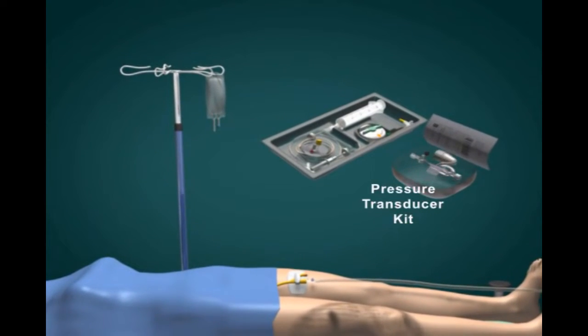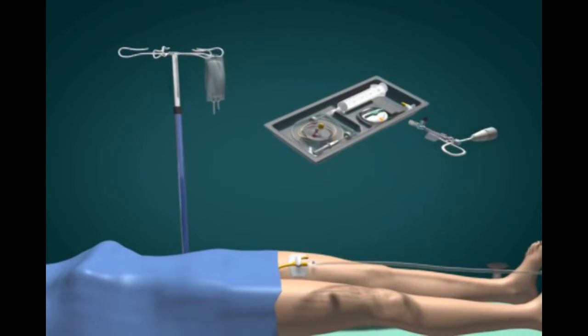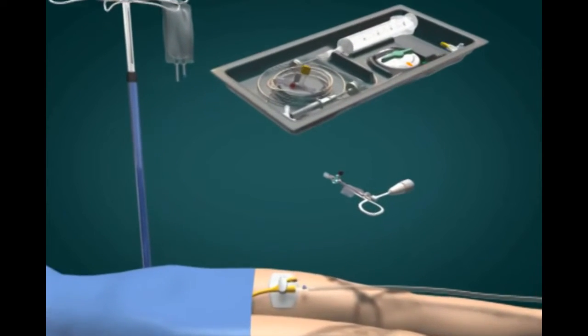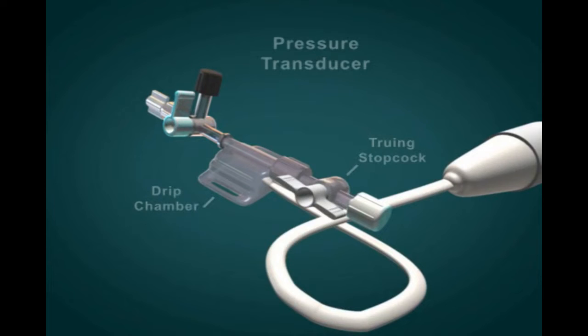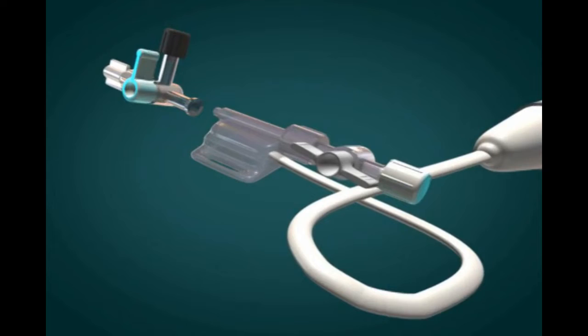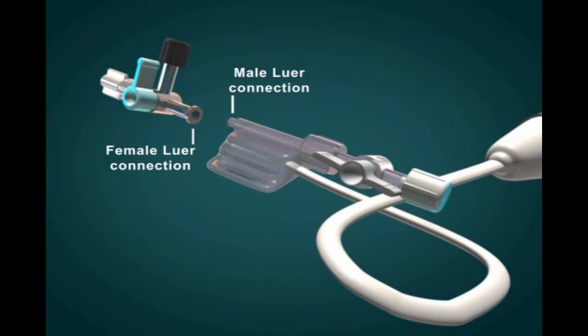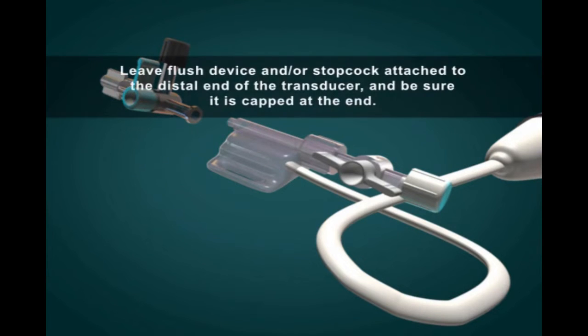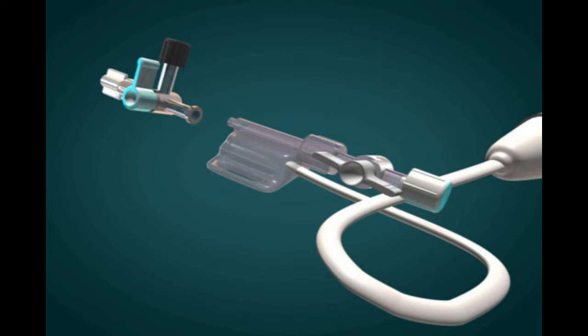Open a pressure transducer kit, not included, in sterile fashion. Note, the intra-abdominal pressure monitoring device adapts to the pressure transducer used in your ICU. Many pressure transducer variations exist, all of which are compatible with the device. Although a flush device is not required, the device can be used with one. Leave the flush device and/or stopcock attached to the distal end of the transducer, and be sure it is capped at the end.